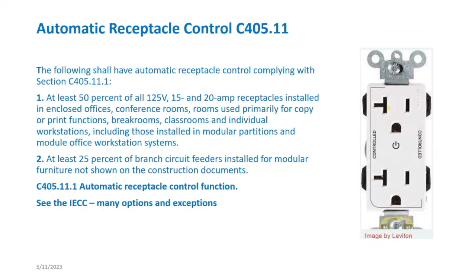That's been in code for a little bit. Automatic receptacle control was in ASHRAE only until the 21 code, and now at least 50% of the 125 volt, 15 and 20 amp receptacles installed need to be controlled. If it's modular cubicles, at least 25%. It's simply to shut power off when everybody leaves.